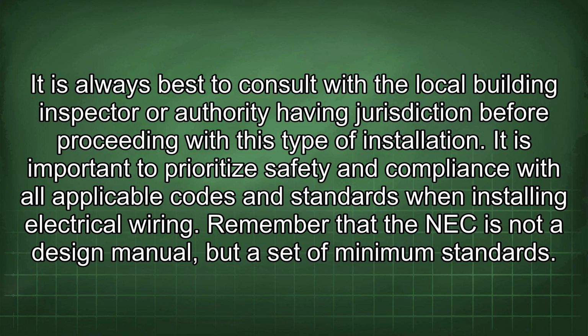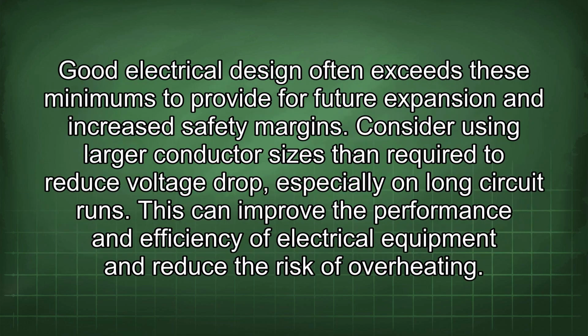Remember that the NEC is not a design manual, but a set of minimum standards. Good electrical design often exceeds these minimums to provide for future expansion and increase safety margins. Consider using larger conductor sizes than required to reduce voltage drop, especially on long circuit runs. This can improve the performance and efficiency of electrical equipment and reduce the risk of overheating.